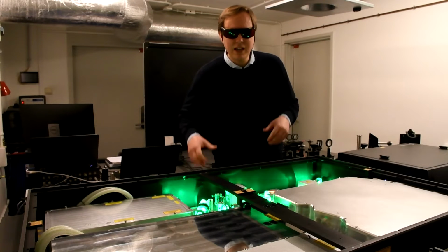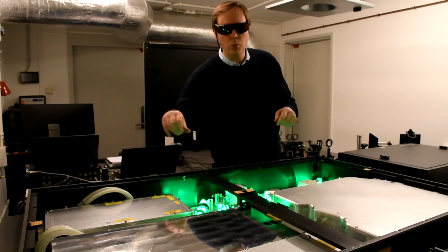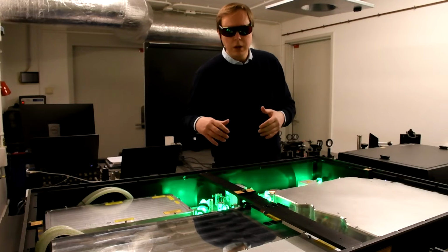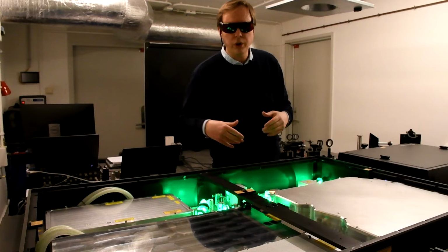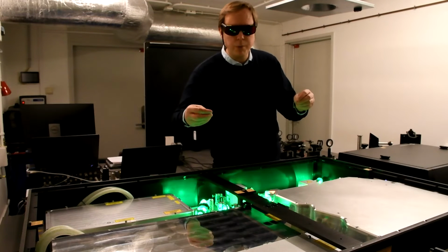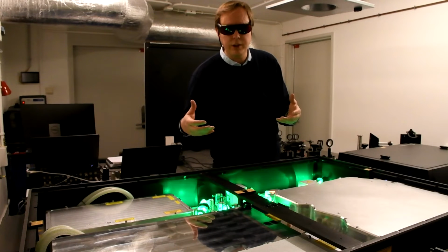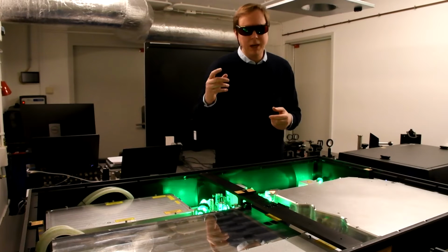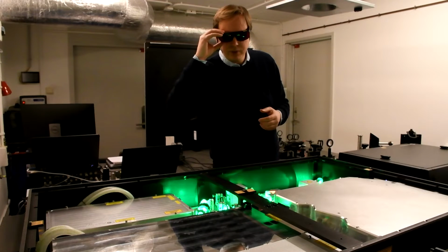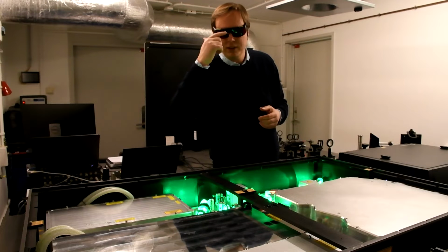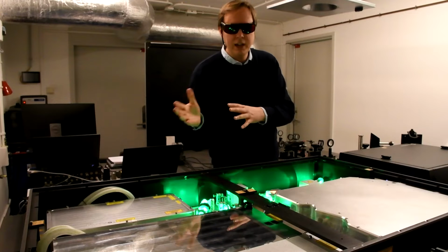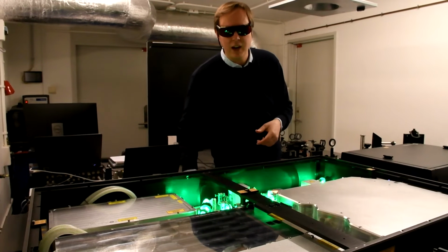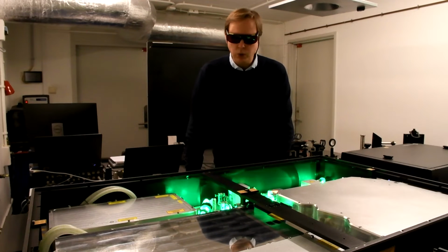Okay, so now we're inside the laser. We have opened the lid, and we have actually tripped the interlock, meaning that we can run the laser while we do some work here. Sometimes you need to go in and optimize a couple of mirrors to pick up the beam power and so forth. But of course we're in the laser lab, so that's why I need to wear goggles now. I have this optical density for all these wavelengths that are included. You see the green light, but you also see a faint red light. I will go through everything here.